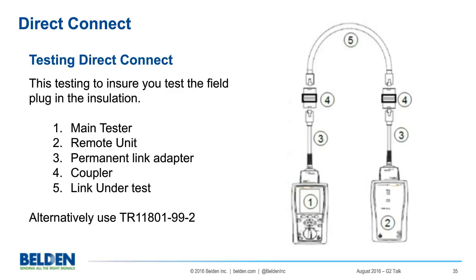Alternatively, you can use ISO limits available on some testers. This test is TR 11801-99-2. It's not a spec yet. It's going through the balloting process. It utilizes patch cord adapters, but does the calculation to include the plug on the end of the channel.